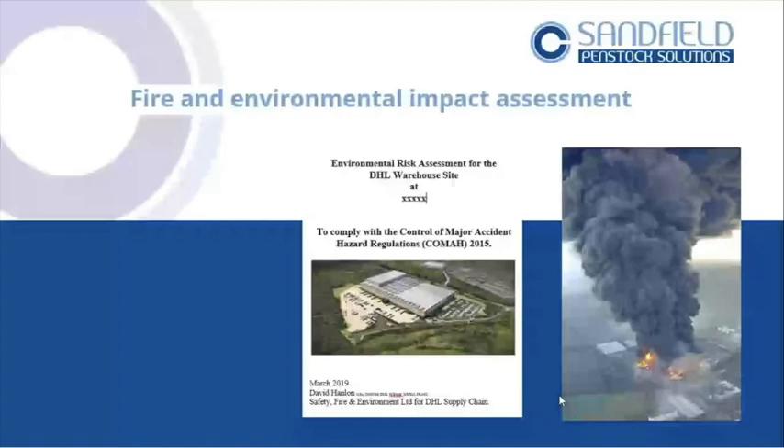Getting good images of the drainage. We fill in drainage cards — lifting the manhole, measuring the pipework, the depth, and the chamber dimensions, because that potentially becomes the catchment volume. That gully manhole we've got there could probably contain, if isolated, a thousand litres of a chemical. It allows us to develop what we're actually looking for. It might just be that we want localised control — the asset's already there, we just need to isolate it and turn it into a temporary tertiary catchment point.